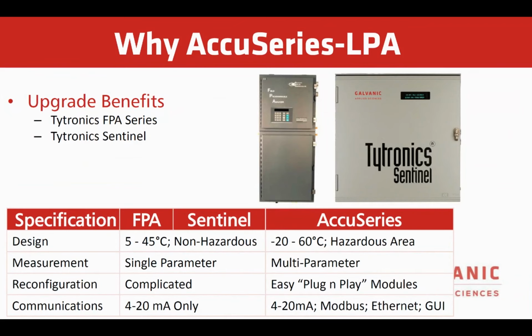Here we're looking at some of the upgrade benefits. So if you were a customer that had an old FPA or Tytronics Sentinel, obviously the design now has changed. Our temperature limitations are much better. The old FPA and Sentinel would only work really well at ambient temperatures between 5 and 45 degrees C. AccuSeries now is rated to -20 to 60 degrees C. And we can meet hazardous area without a purge, as opposed to the Sentinel FPA, which would require a purge on them.